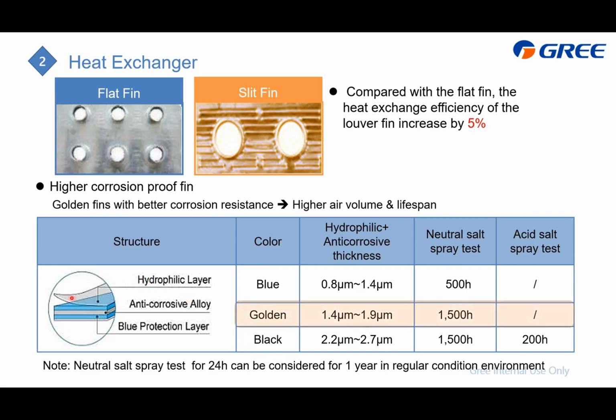And here are the fins. Inside it there are 3 layers. Actually these 3 layers are for different levels. The difference is just the thickness. And if the thickness is different, the anti-corrosion level is also different. And for this golden, it is standard. It can last 1,500 hours in the neutral salt spray test.